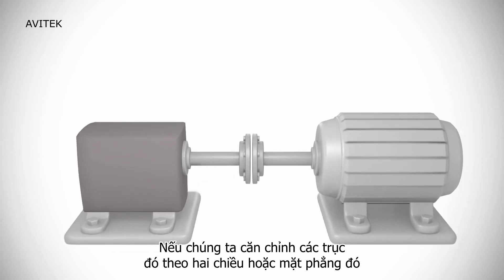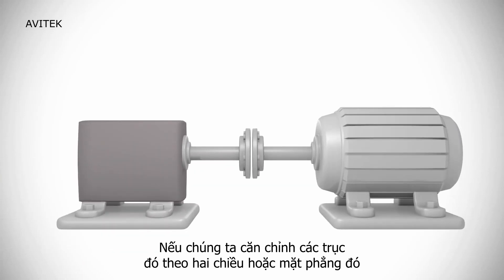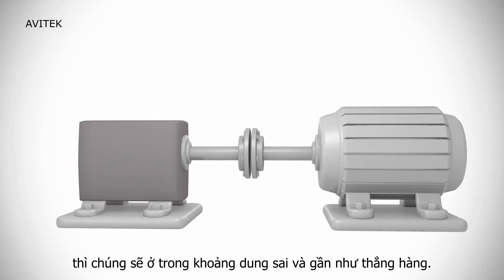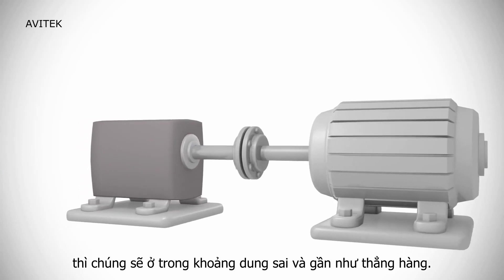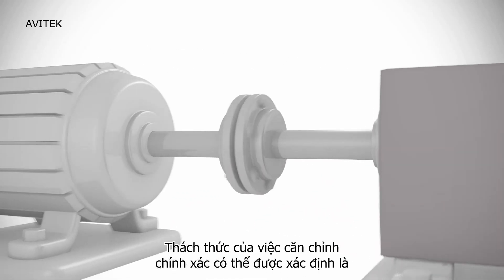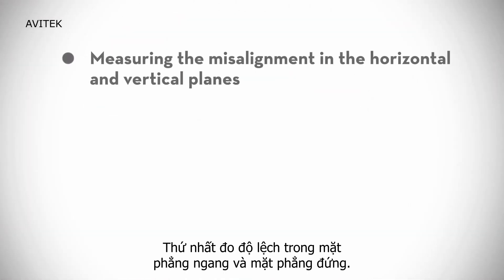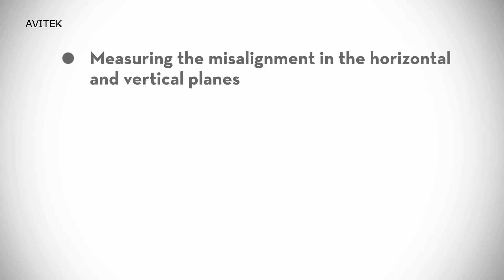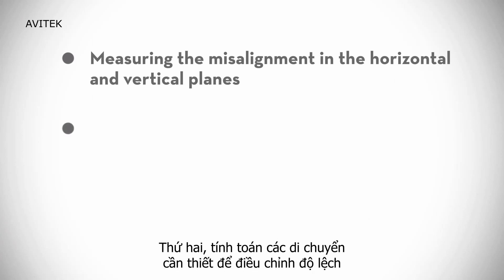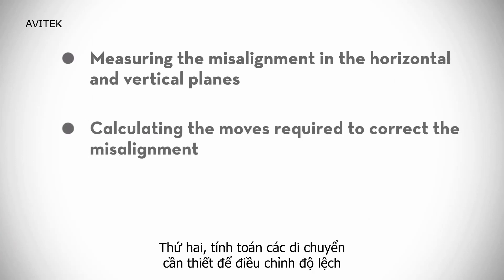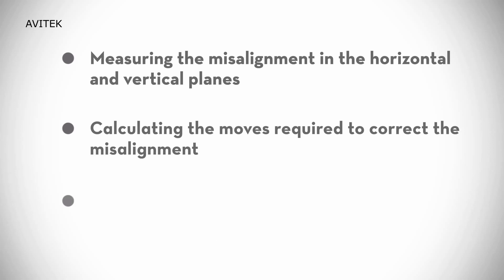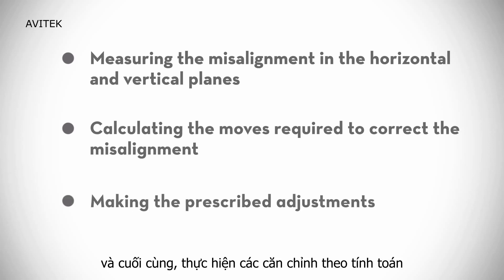If we get the shafts aligned in these two dimensions or planes, they will then be within tolerance and close to collinear. The challenge of precision alignment can therefore be defined as: first, measuring the misalignment in the horizontal and vertical planes; second, calculating the moves required to correct the misalignment; and finally, making the prescribed adjustments.